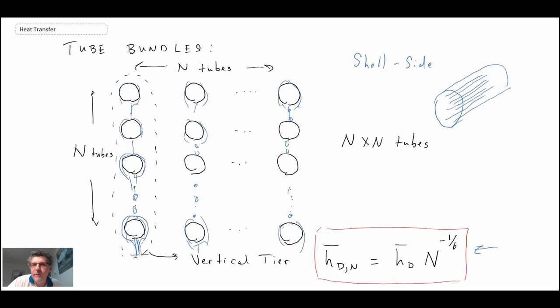Now, if it was tube side condensation, then we would be looking at a condensing unit where we have the condensation occurring on the inside of the tubes. And sometimes there'll be a little slope and the liquid will build up. If you're to look at the cross section of this, what's happening is you get the film building up on the inside, it runs down the walls, and then you get a layer of liquid forming on the bottom.